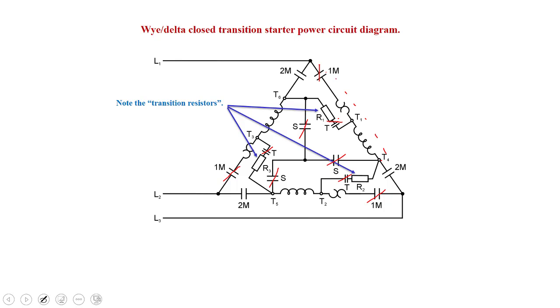Then our star contacts would open. Now this happens very quickly. So these motor windings are always going to have some voltage, some sort of current going through them, or a supply on them during this period. Next thing to happen is that 2M contacts will close. And the last sequence is the transition resistors will open up.